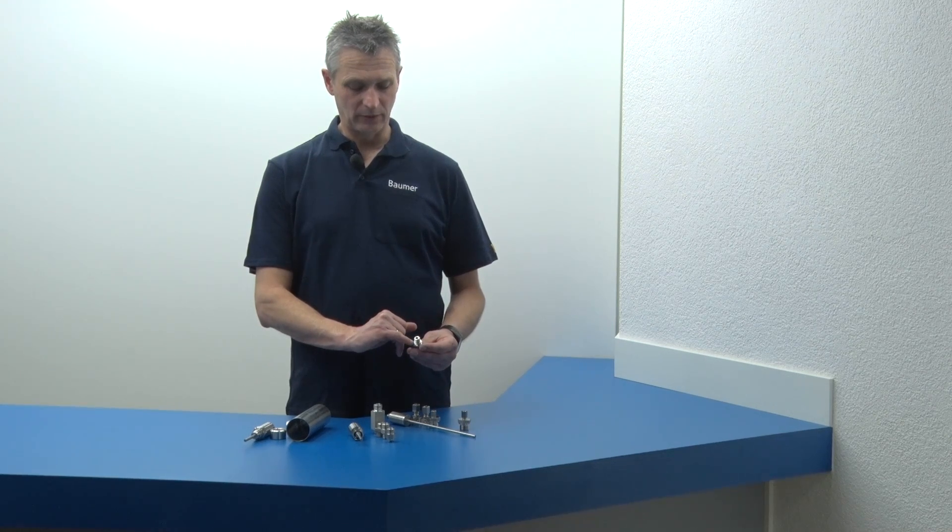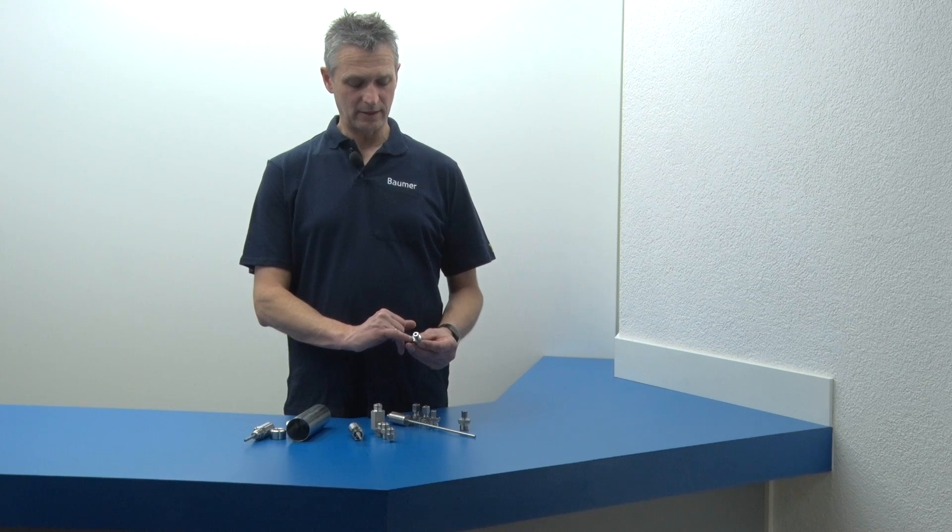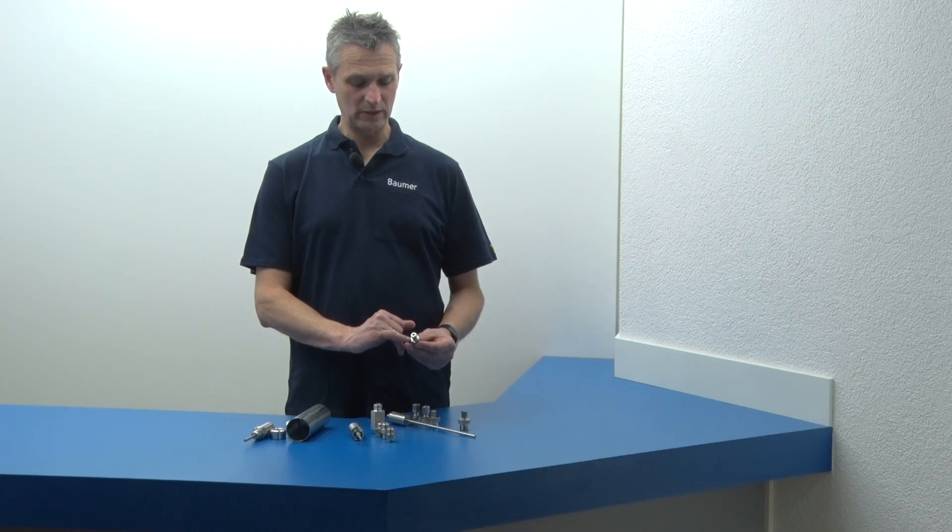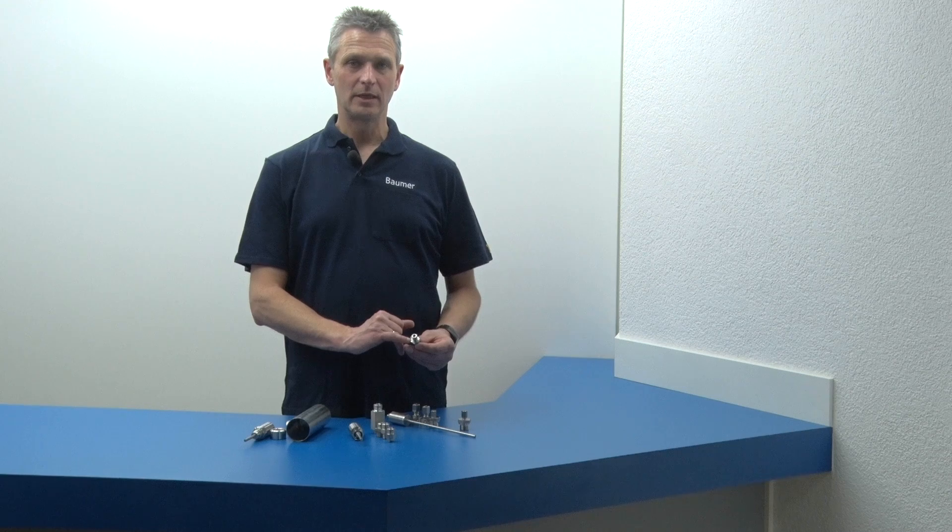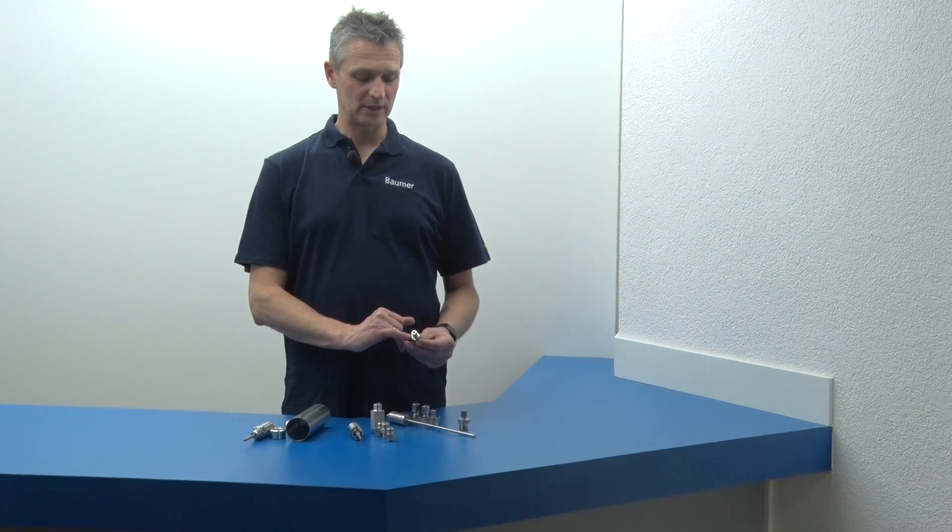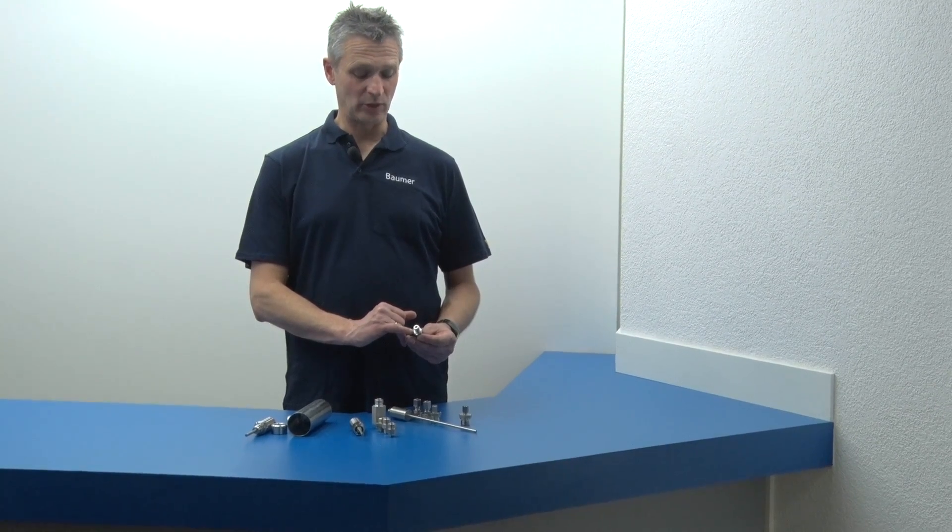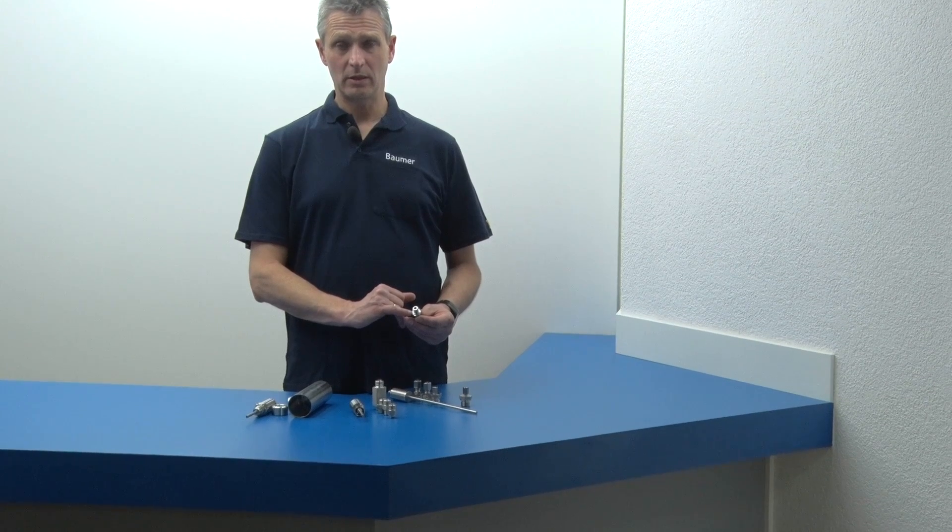The screw adapters are pre-dry greased. This allows to install and remove the process connection up to 20 times without danger of cold welding between the stainless steel parts.